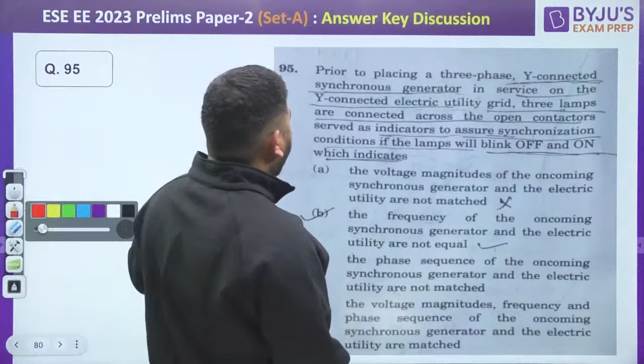Next question: prior to paralleling a 3-phase Y-connected synchronous generator with a Y-connected electric utility grid, 3 lamps are connected across the open contactor to serve as synchronization indicators. If the lamps blink on and off, what does that indicate? It means voltage is the same, but the frequency of the incoming machine is not the same as the utility. So the answer is B - the frequency of the oncoming synchronous generator and the electric utility are not equal.